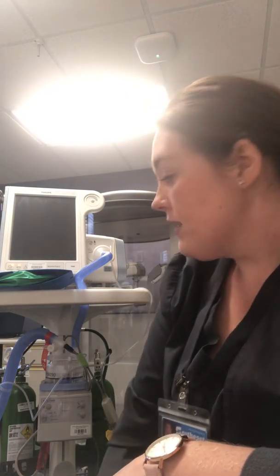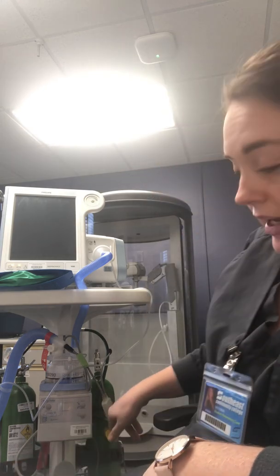You do want to make sure that it's plugged into the red outlet, so it's attached to the backup generator. This type of system does use oxygen, so you can attach oxygen to the wall outlet. You can also see I have two E-tanks with the regulator, so you can also attach to those for transport, etc. I will not be using oxygen as part of my video, but just know that you do use oxygen with a Bipap, and Bipaps can be heated humidity or not. This particular setup that I have here is for heated humidity.